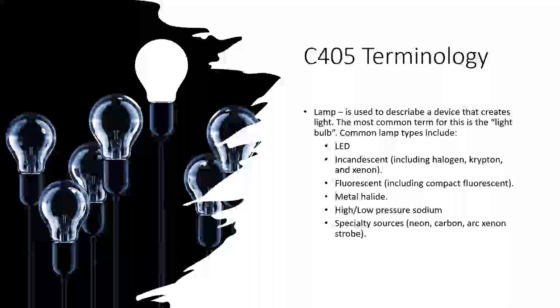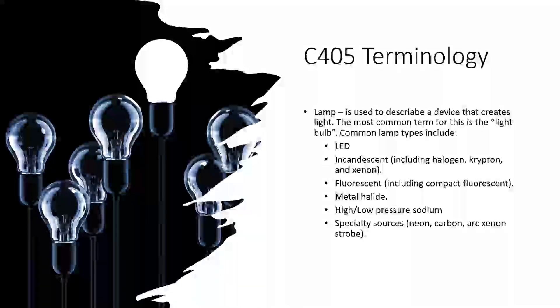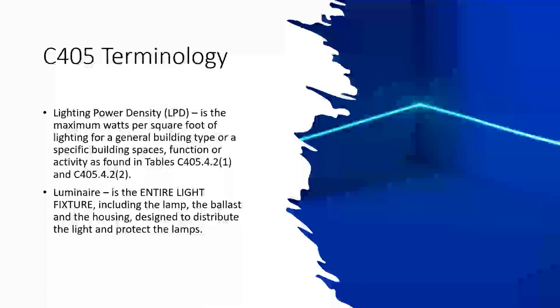The term 'lamp' refers to what we would call a light bulb. Even though LEDs have diodes, we still refer to them as lamps — a series or linear row of diodes in a fixture is still one lamp. It includes LED, incandescent, fluorescent, metal halide, low sodium, high sodium, and specialty sources. Another important term is lighting power density, or LPD — the maximum watts per square foot of lighting for a general building type or specific space. There are tables that correlate it depending on whether you're using the building type or space-by-space method. When I say 'luminaire,' I'm referring to the entire light fixture — the bulb, housing, ballast, everything designed within it.